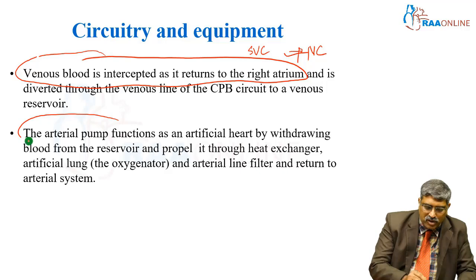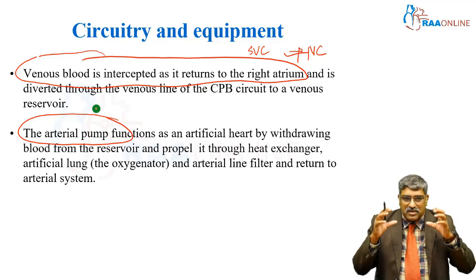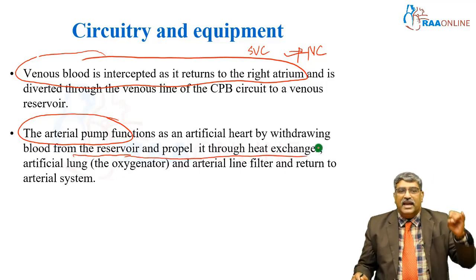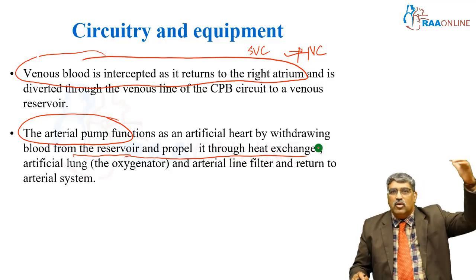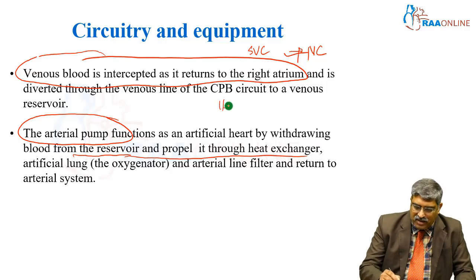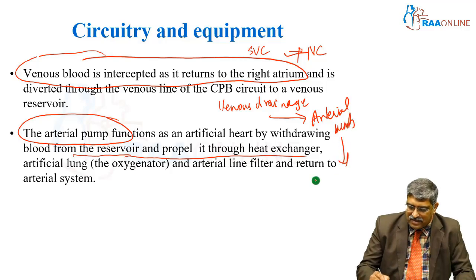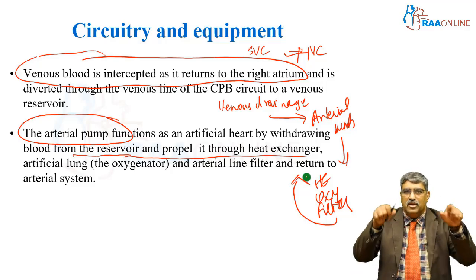From the venous reservoir, the blood goes into the arterial pump, which functions like an artificial heart. The blood received from the reservoir is propelled through the heat exchanger, oxygenator, and an arterial line filter, and then goes back into the circulation. This is the usual circuit.